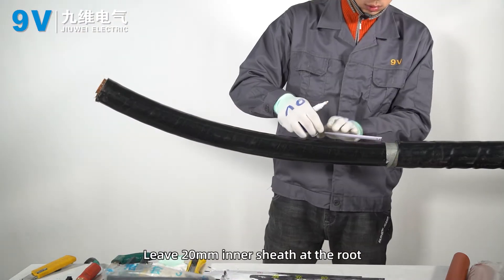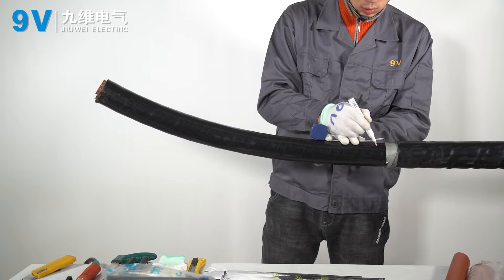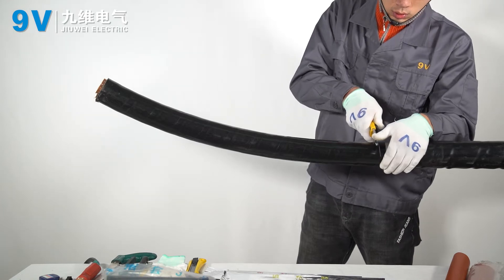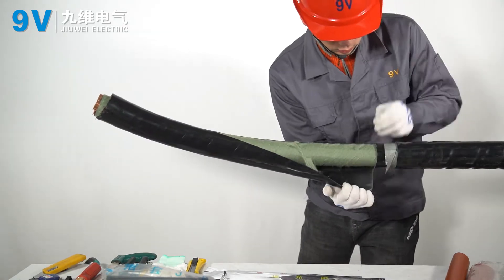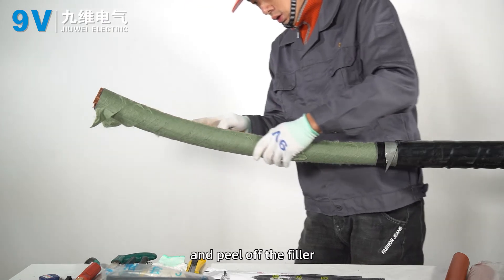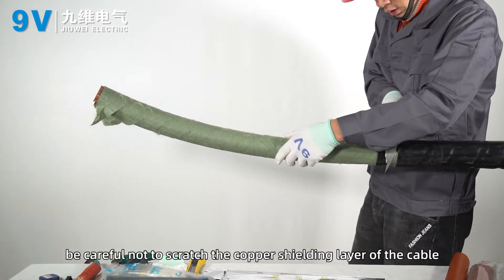Leave 20mm inner sheath at the root. Peel off the inner sheath of the other cables and peel off the filler. Be careful not to scratch the copper shielding layer of the cable.